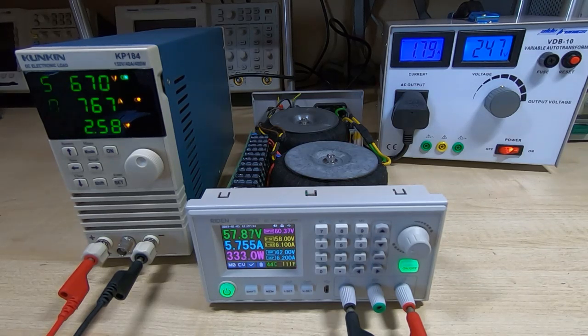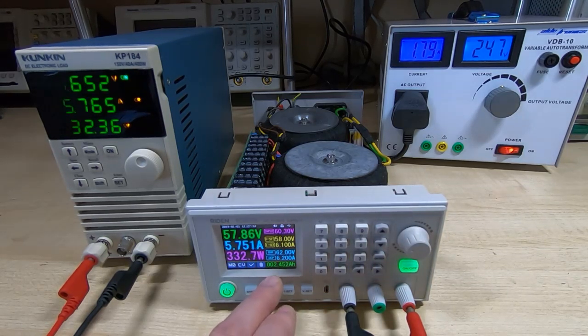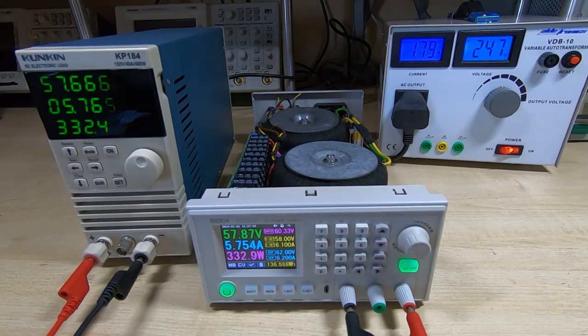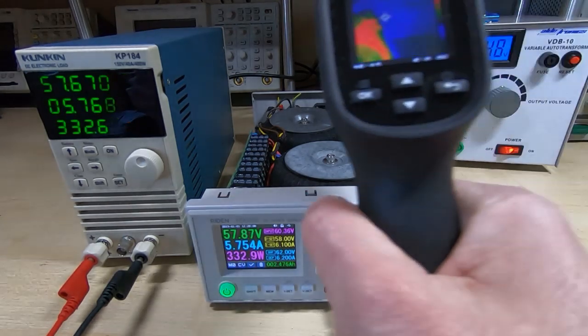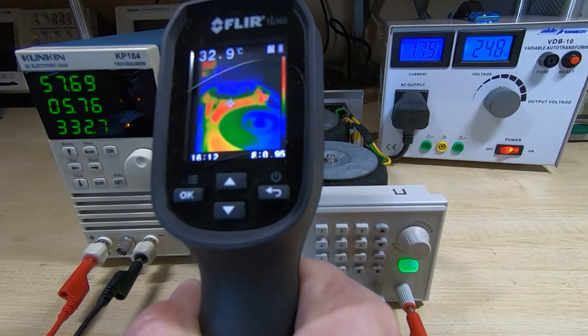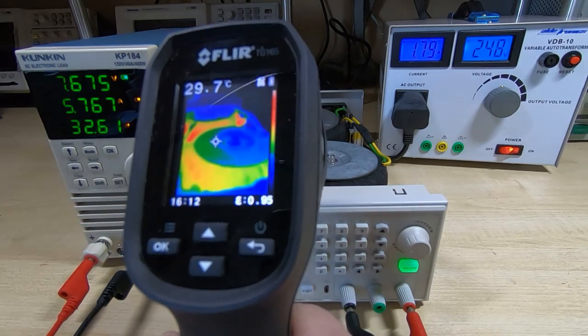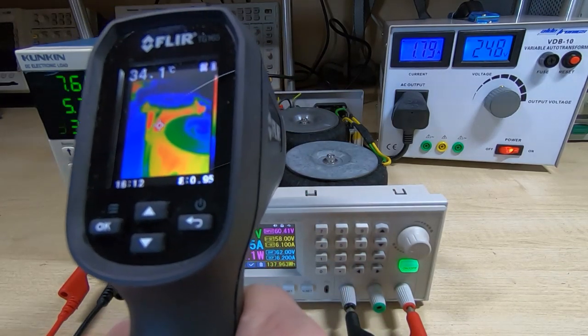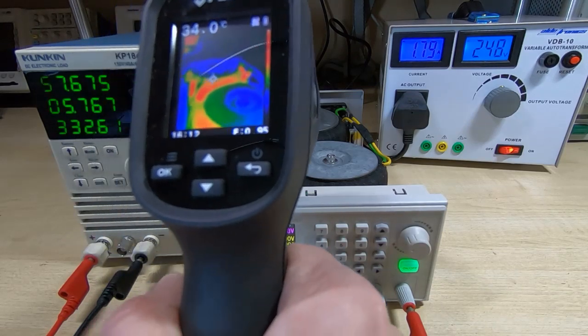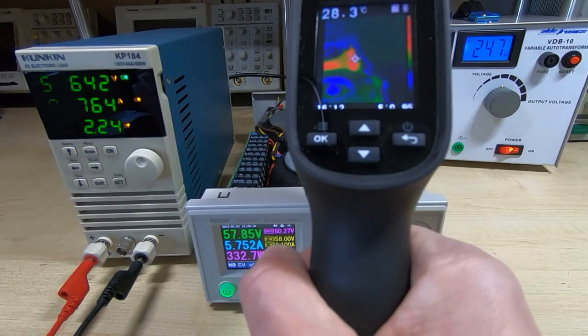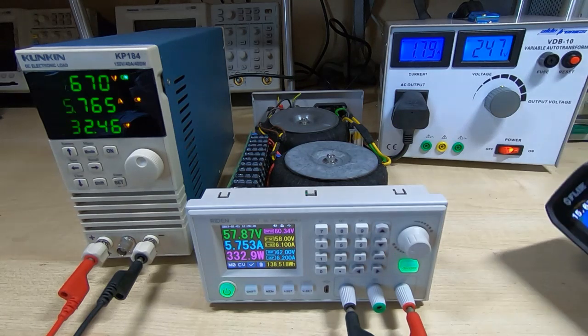What you'll notice here is that the temperature down here, the hottest temperature in the system, is the rectifier heatsink, around 44 centigrade, and it's stabilized there - not rising anymore. If we look through the thermal camera, everything is fairly cool. The only things getting warm at all are actually the thick cables, the thick copper wires between the transformers.